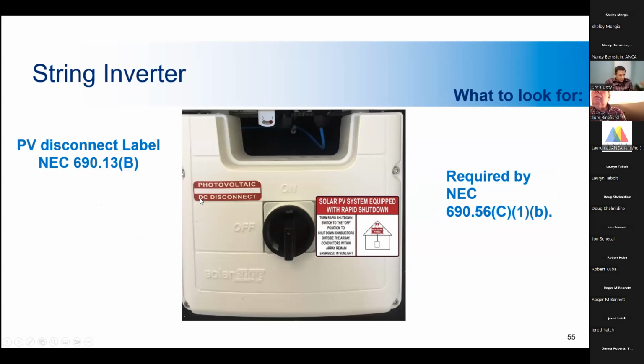So you can see that here it's PV DC disconnect and it has the rapid shutdown. Labeling is very important for future maintenance, and electricians working on the system, so they'll be aware of the specific hazards that the inverters or the enclosures have, and it also applies to first responders.